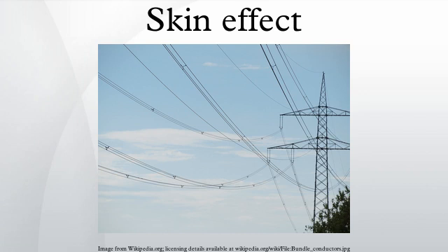Material effect on skin depth. In a good conductor, skin depth varies as the inverse square root of the conductivity. This means that better conductors have a reduced skin depth. The overall resistance of the better conductor remains lower even with a reduced skin depth. However, the better conductor will show a higher ratio between its AC and DC resistance, when compared with a conductor of higher resistivity. For example, at 60 Hz, a 2000 mcm copper conductor has 23% more resistance than it does at DC. The same size conductor in aluminum has only 10% more resistance with 60 Hz AC than it does with DC.